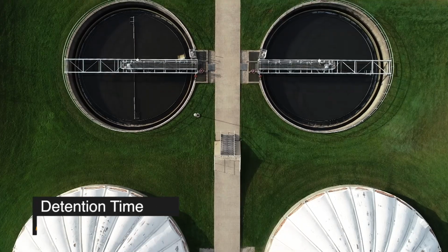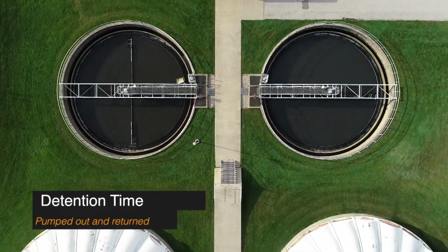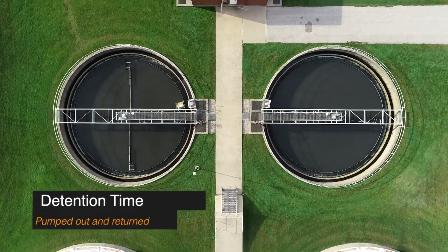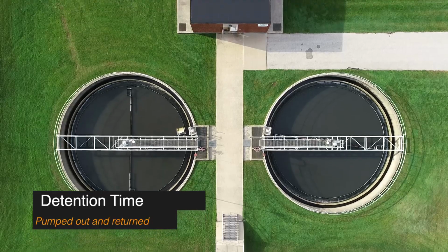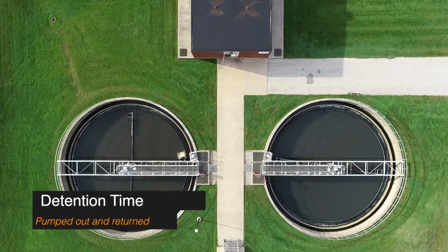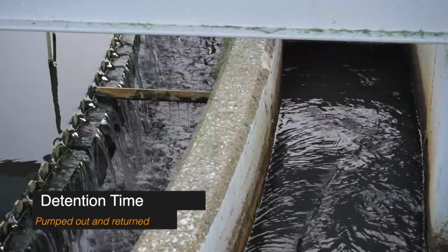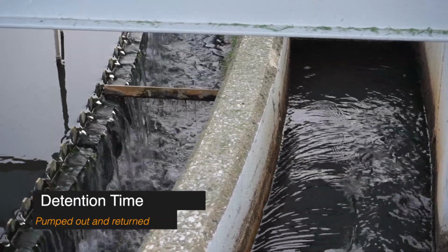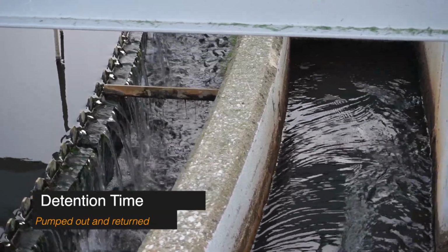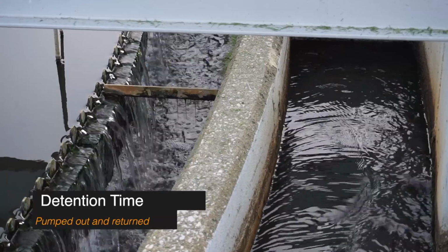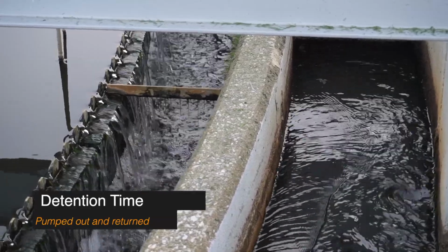Here the water is provided detention time for settling. Detention time allows the solids, including sloughing of the old dead microorganisms, to settle to the bottom of the tank. Sweep arms at the bottom of the tank pull the settled solids to a sump where it is pumped out and returned to the primary settling tanks. Any excess floc that passed through the primary tanks is removed here. This allows only clear water to exit the clarifier.